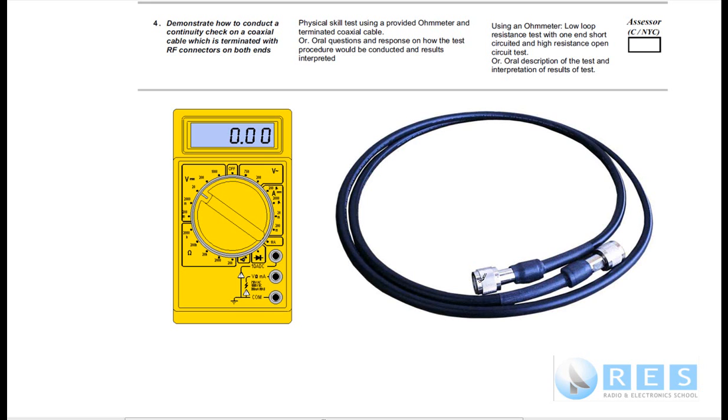The next test is to check that there's actually continuity between the shield at this end and the shield at that end, and also continuity between the pin at this end and the pin at that end. To do that we use a low ohm scale because we're expecting to find a very low resistance. First when we measured between the center conductor and outer conductor, we did a high ohm scale and expected to find infinite resistance because they shouldn't be touching.